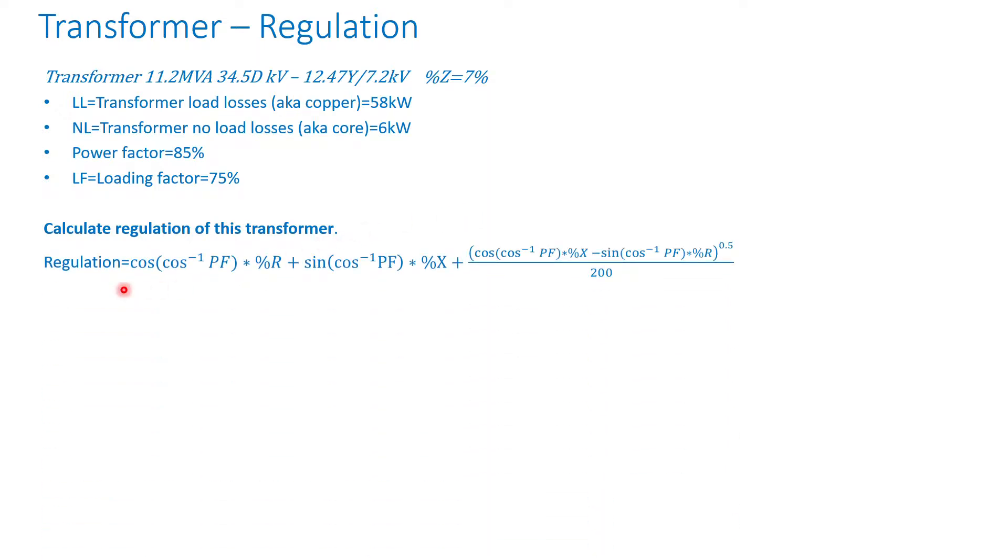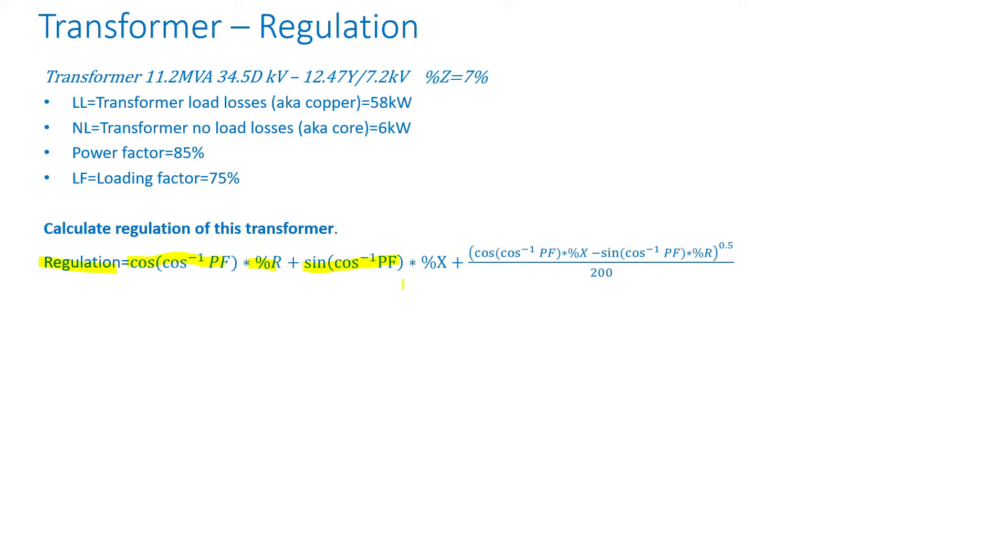So the voltage regulation formula is equal to cosine of the inverse cosine power factor times percent resistance plus the sine of the inverse cosine of the power factor times the percent reactance plus square root of cosine of the inverse cosine of the power factor times the percent reactance minus sine of the inverse cosine of the power factor times percent resistance divided by 200.